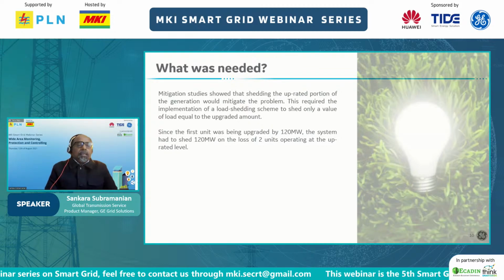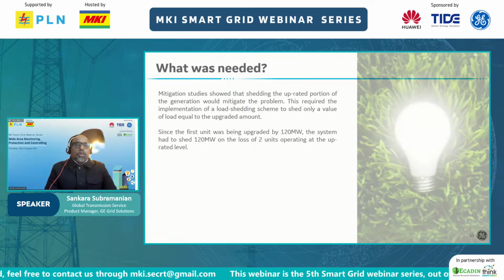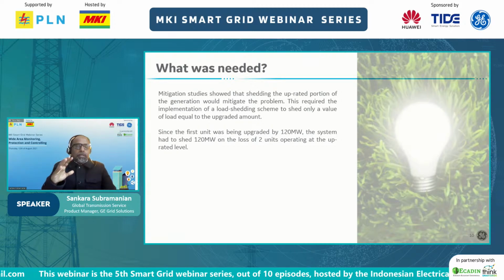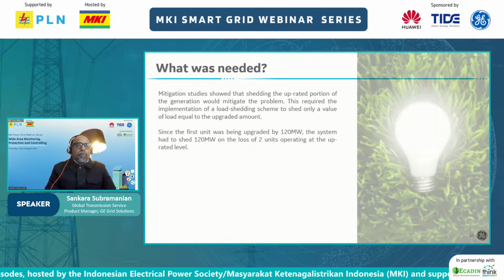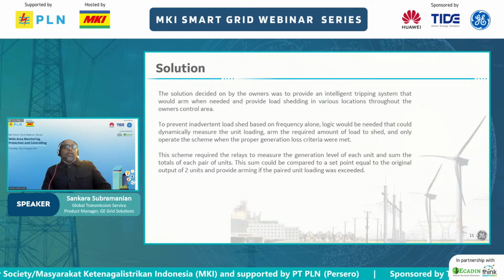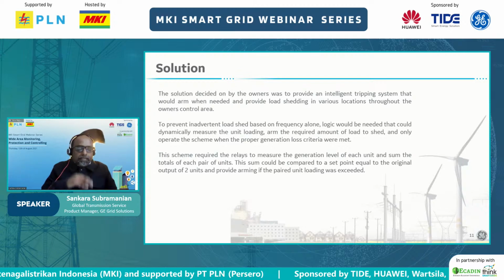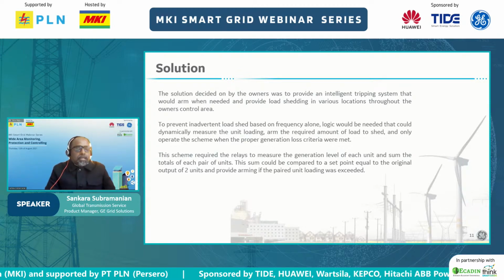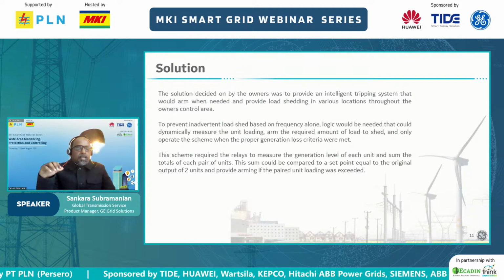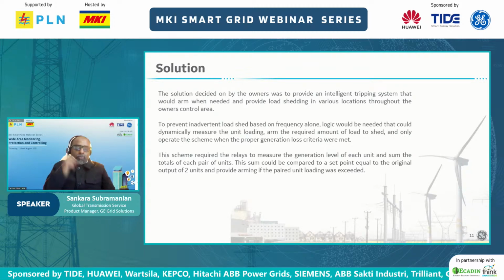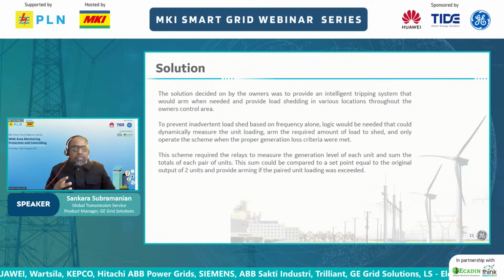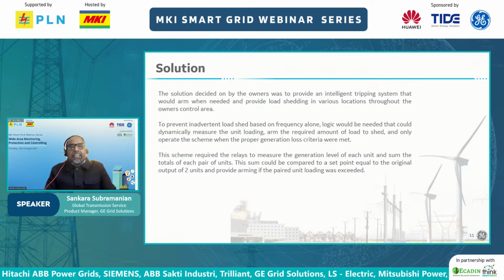That's when the mitigation studies were done, and they showed that if we mitigate this extra 120 megawatts that has been up-rated, and the loss of these 2 units, by performing load shedding operations, that would maintain the system. So the owners decided to provide an intelligent system of load shedding in various locations throughout the local area to prevent inadvertent load shedding just on frequency. They also included the power criteria.